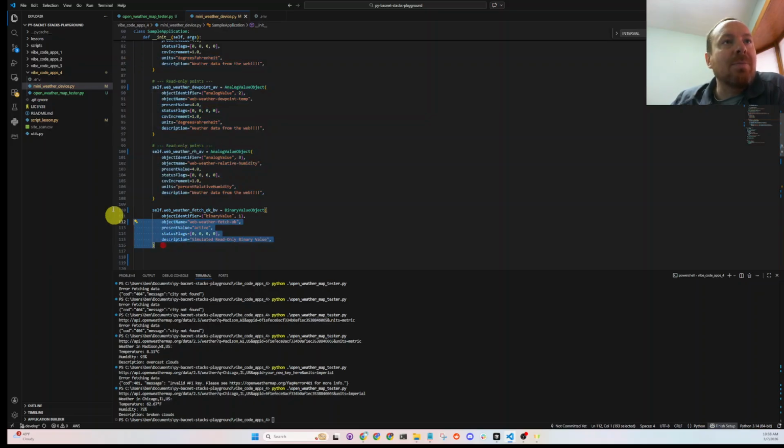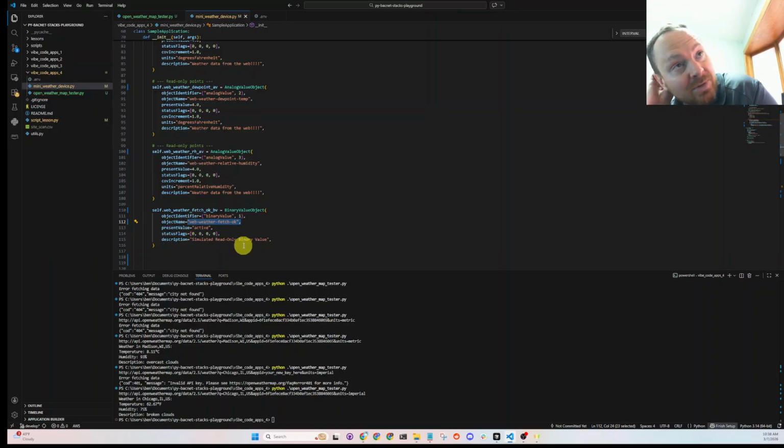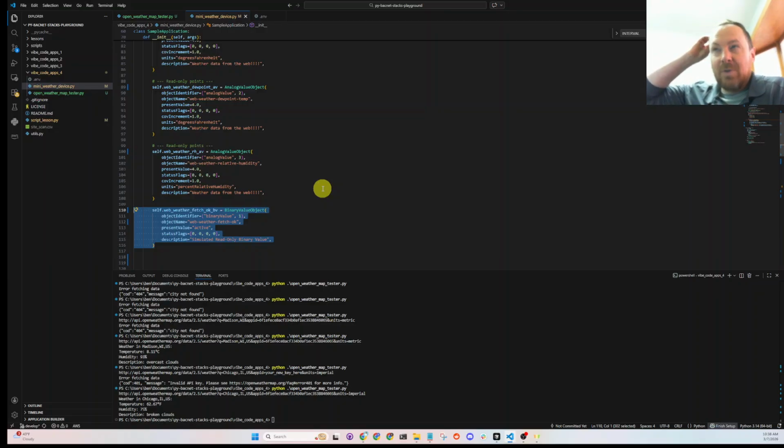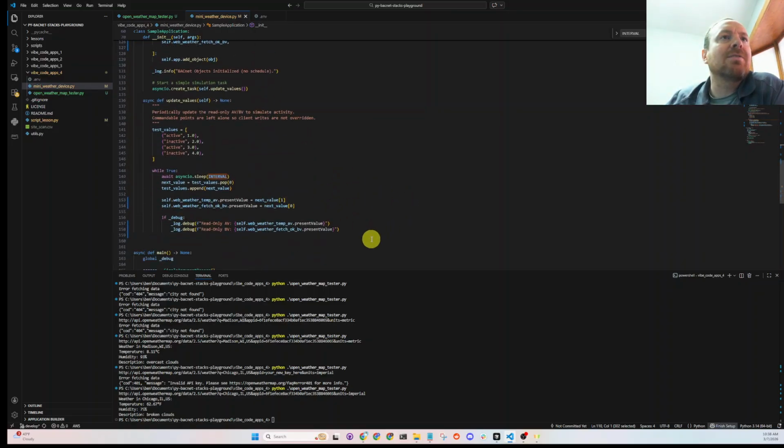We could have a BACnet Boolean point that would just go false, meaning the weather fetch data failed. And what you could do on the building automation side is wire in logic that if this is false or bad, use the local building sensors. There are ways we could get really fancy and make it stale somehow, but whatever, this is just mimicking something kind of cool to try.